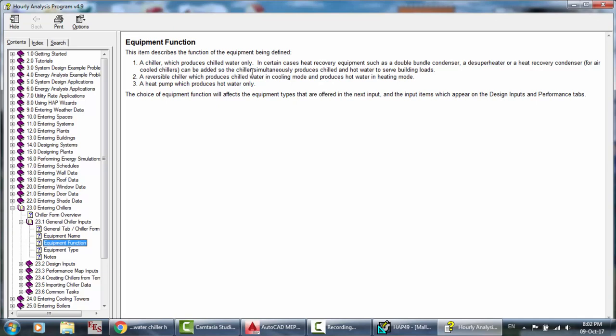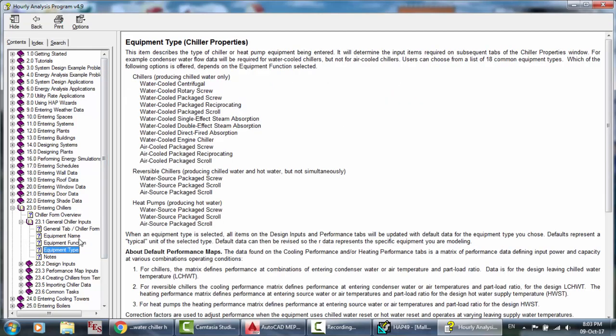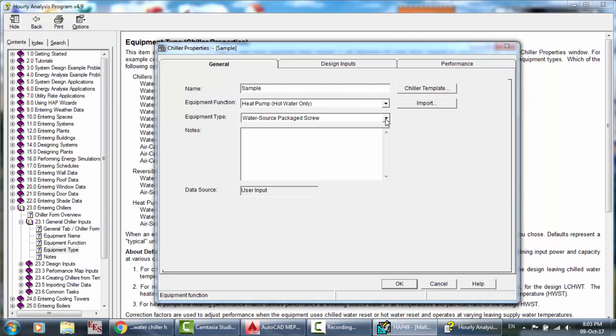The equipment function defines what the chiller produces. A chiller which produces chilled water only can optionally have heat recovery equipment such as a double bundle condenser or desuperheater so it simultaneously produces chilled and hot water. A reversible chiller produces chilled water in cooling mode and hot water in heating mode. A heat pump produces hot water only. The choice of equipment function affects the equipment types offered and the performance steps available.